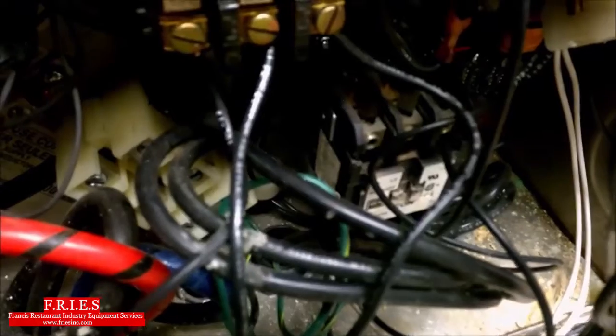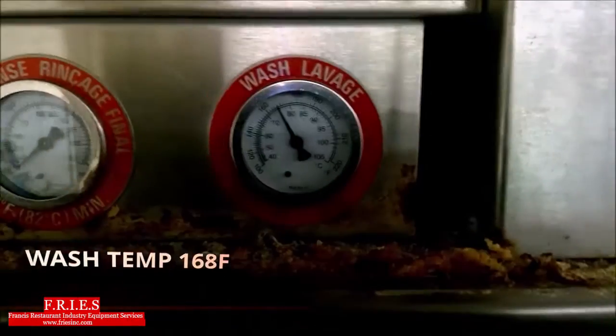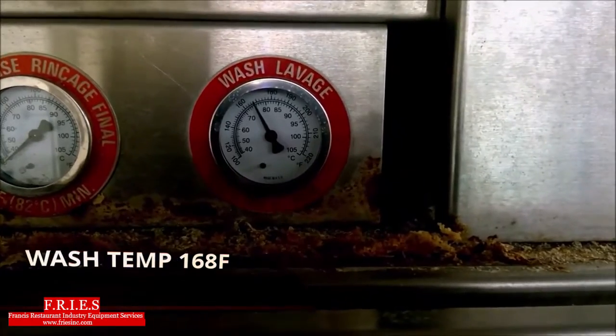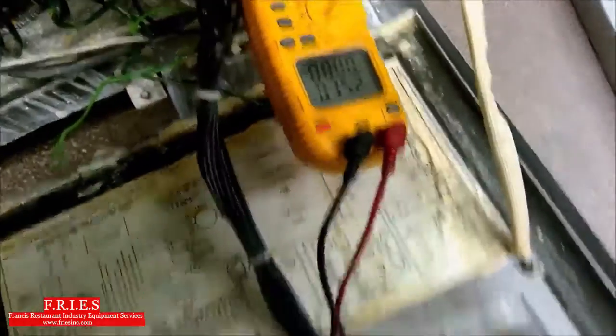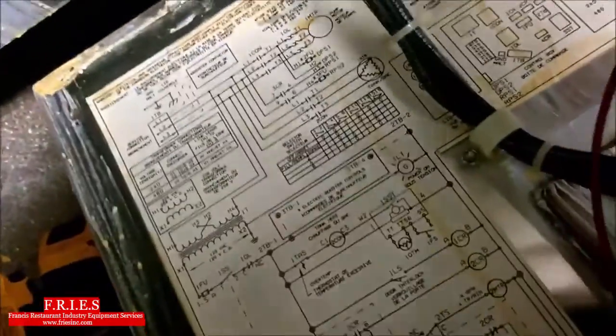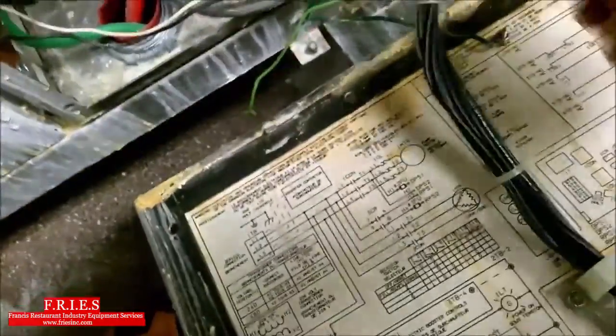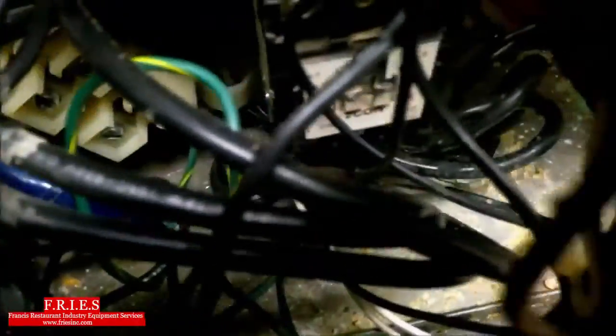Alright, so we've cycled off. Plunger's no longer pulled in. And we cycled off at 168 Fahrenheit. I'm just going to take an amp draw now that the plunger's no longer pulled in to make sure there's no bleed through on this contactor. We want 0 amps across all 3 legs, which we do have.